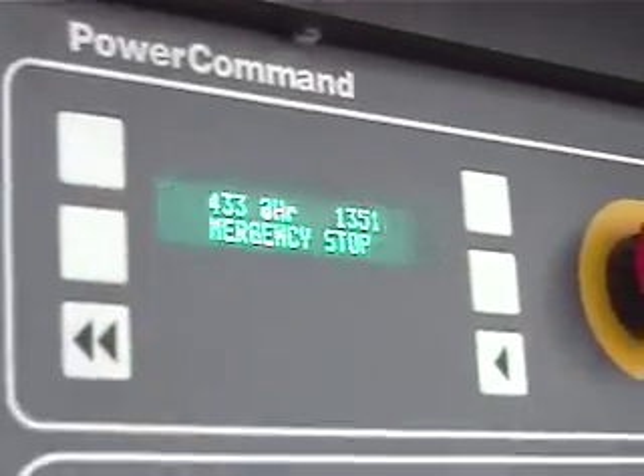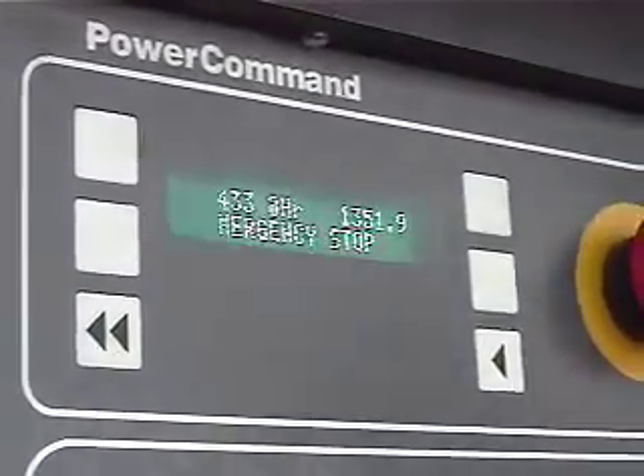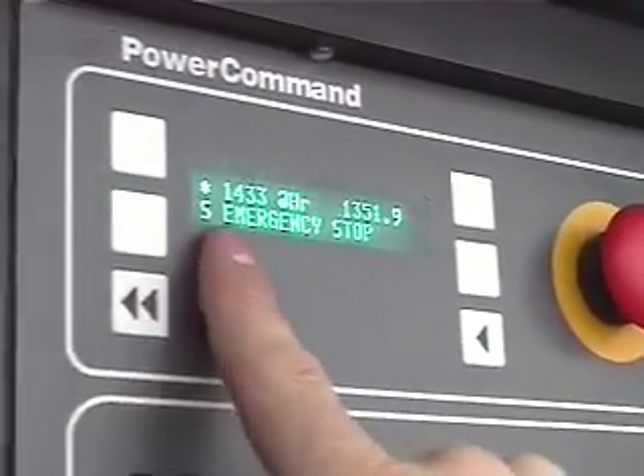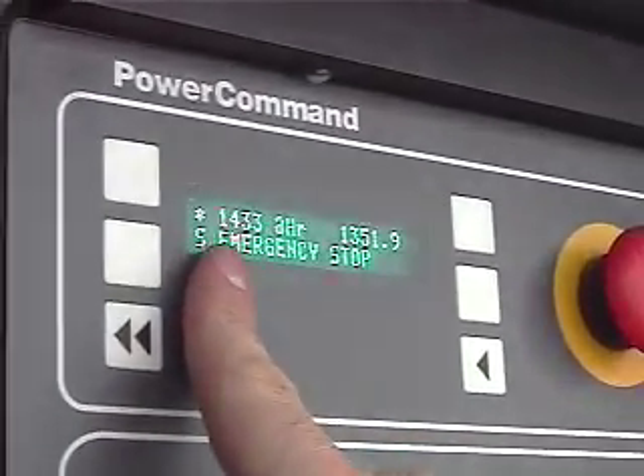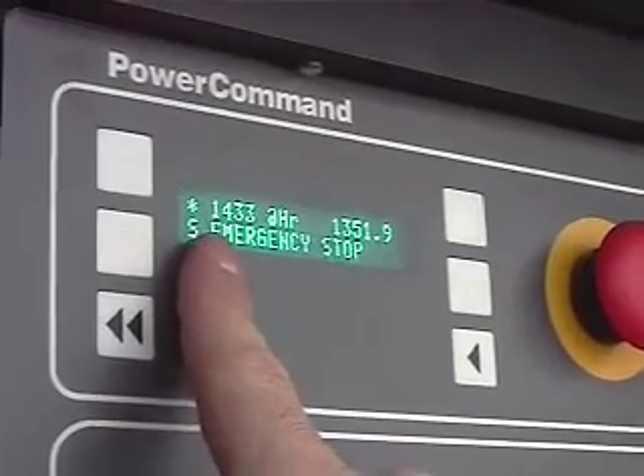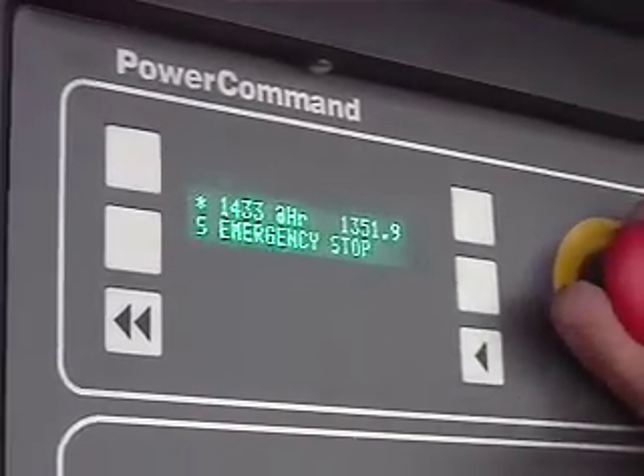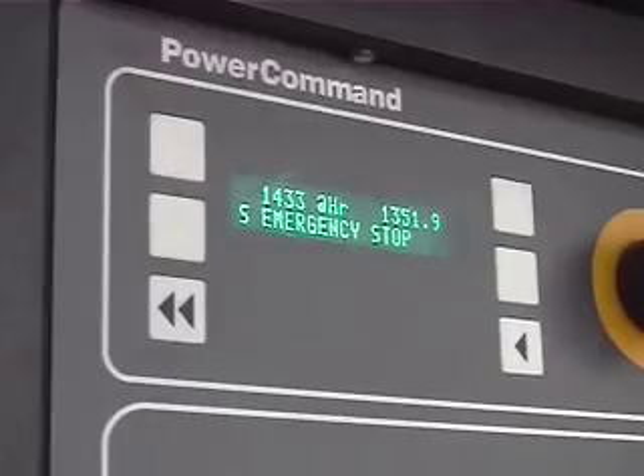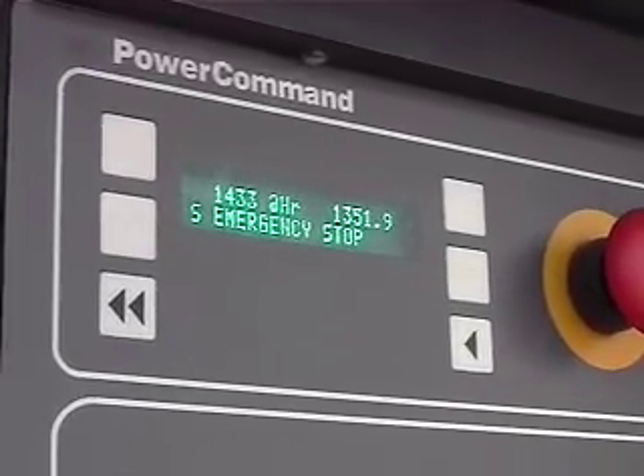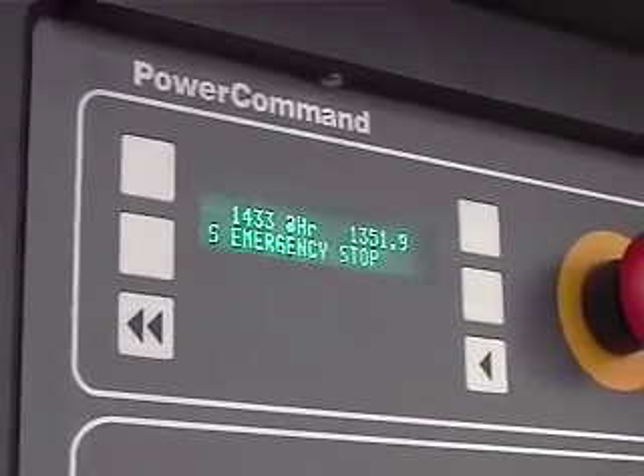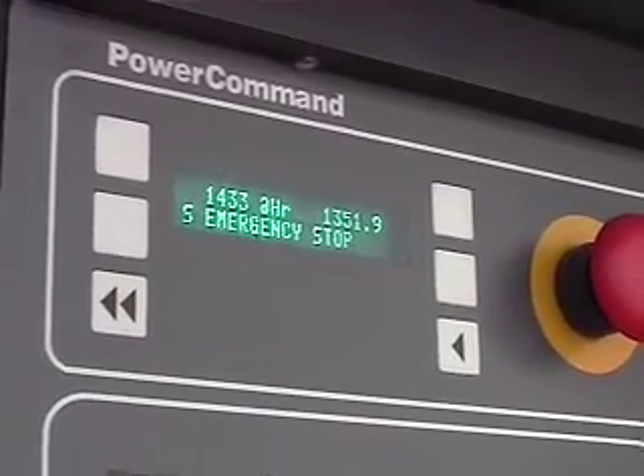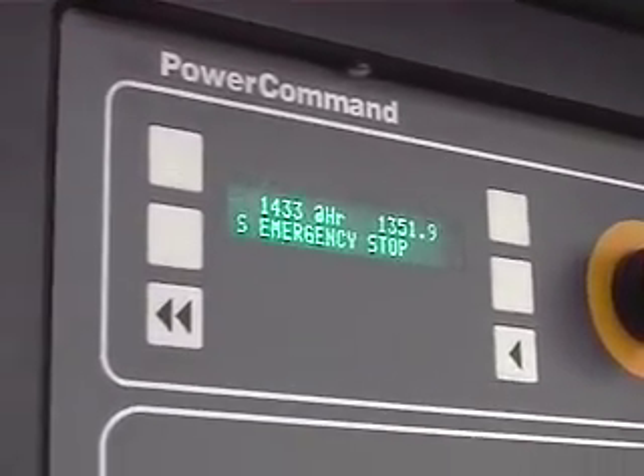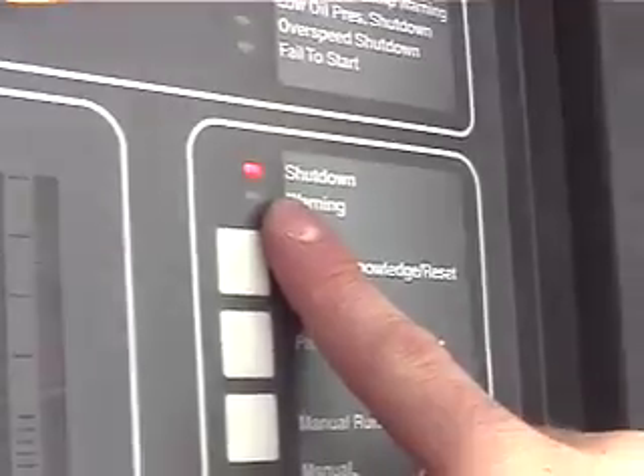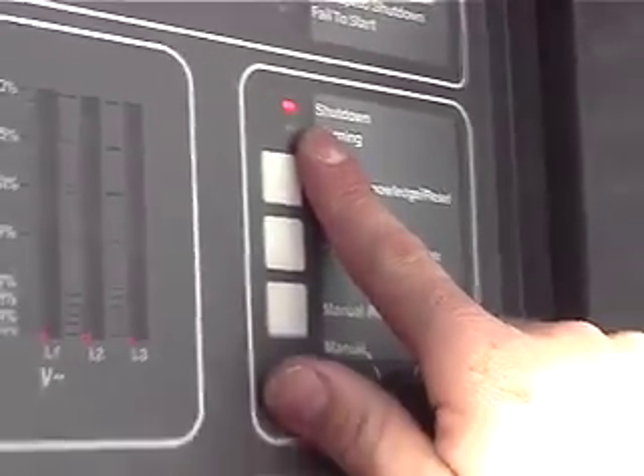Okay, so let me go to the current fault that we have. It's the e-stop button. You have the asterisk, which tells you that it's a current active fault. Now, if you watch the asterisk, when I pull this e-stop button, that asterisk is going to go away. That says that the fault is cleared, it's not active anymore, but it's still shut down. We know it's shut down because we have a shutdown light on over here. As long as that shutdown light's on, it is not going to start.